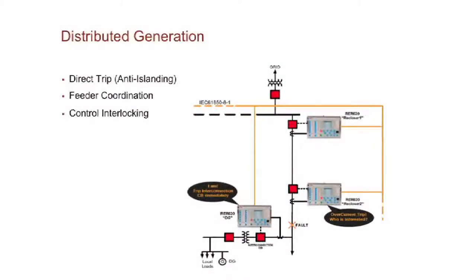So we developed a lot of features on the recloser to address precisely that, and mainly, I would say, there are three. The main one is this: if you have a fault on your network and your recloser went to lockout at 3 o'clock in the morning, you send your crew out there. A lot of what they would do is give the engineers in the morning, or at night, the events. So what happened, right? You also need to download oscillography records, waveforms.